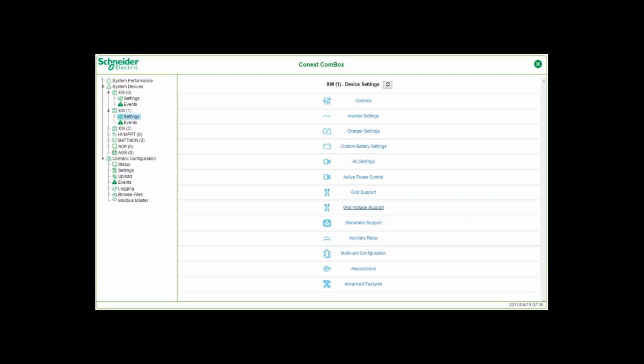You can associate different inverters and different charge controllers to external sources and loads. And then of course advanced features, which gives us parameters such as load shape delay, which allows your system to allow the batteries to recharge before it starts to use battery power. There's other advanced features that we're not going to dive into at this time, but I'd invite you to go into the manual for the XW and check it out.